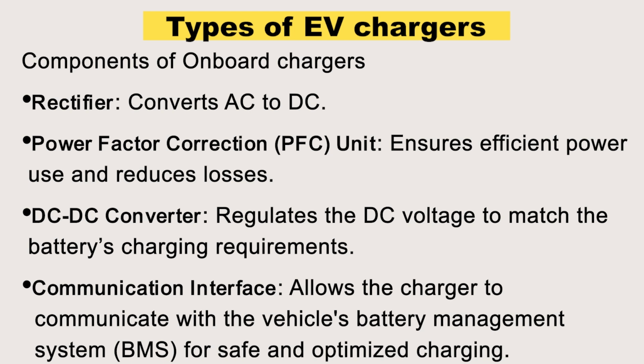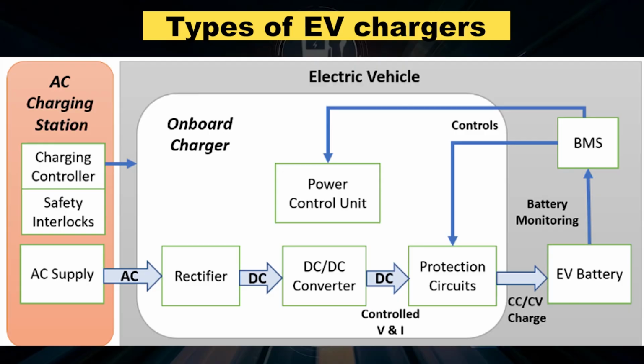They are categorized as constant voltage type loads, and they draw peaky current from the source. So, a power factor correction unit is very essential, as it ensures efficient power use and can reduce losses at the supply side.